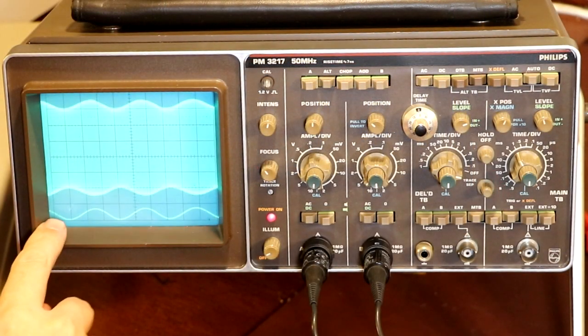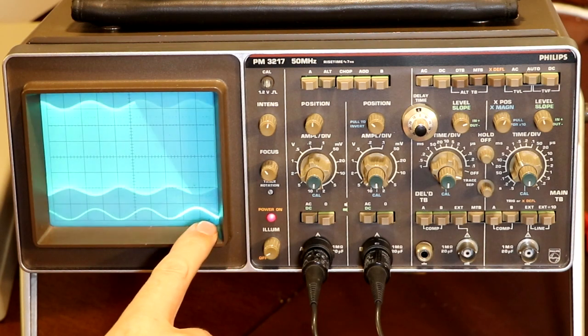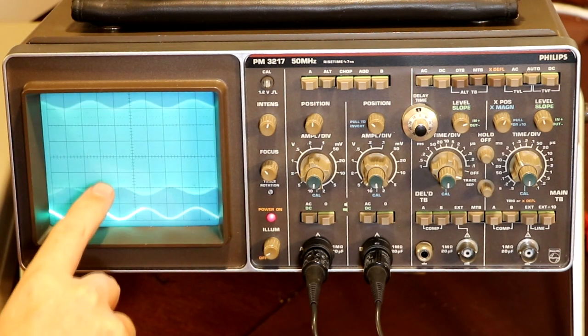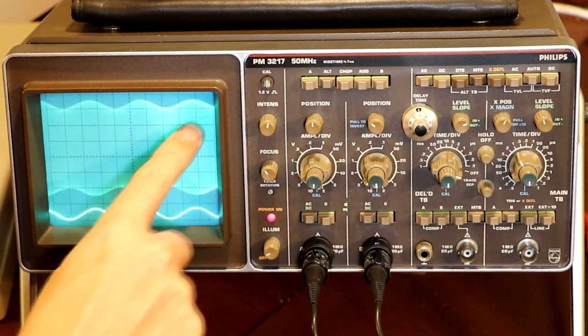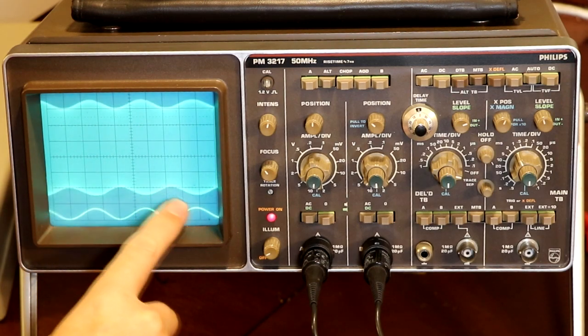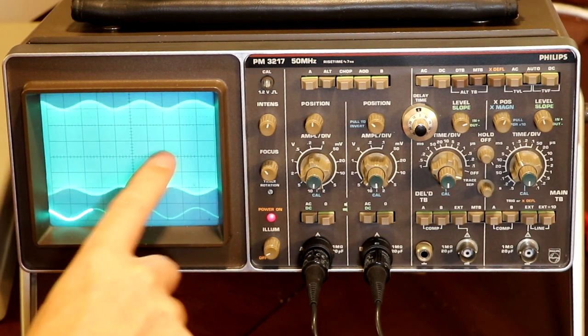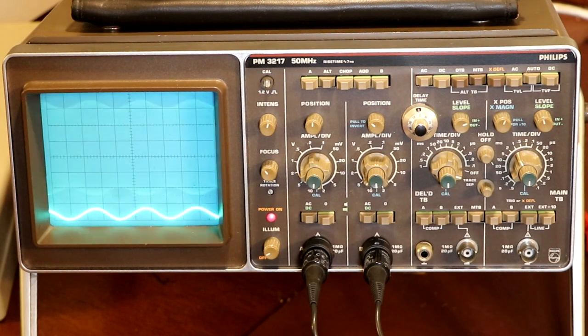Well, I'm hoping that that's going to come out on camera. So you can see we've got the actual low frequency output from the signal generator, and it's modulating the high frequency output here. Now there's not an awful lot of modulation on here. It's certainly not as much as I expected. I seem to think it might have said about 40% on them in the operating manual. Well, that's nowhere near 40% modulation.